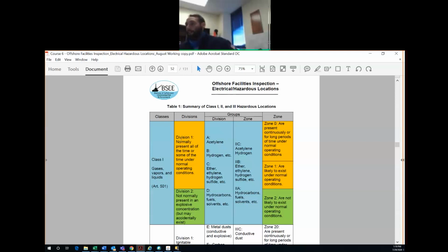And the other thing it'll give is a group. And by group, I mean a letter, A, B, C, or D, or A, B, C, and D. And what that's telling you is that it's not only rated for the division, but it's rated for the gas or ignitable thing that is going to be in that division. And they classify these different types of flammable gases into 4 different groups in the 500. And those groups are A, B, C, D.